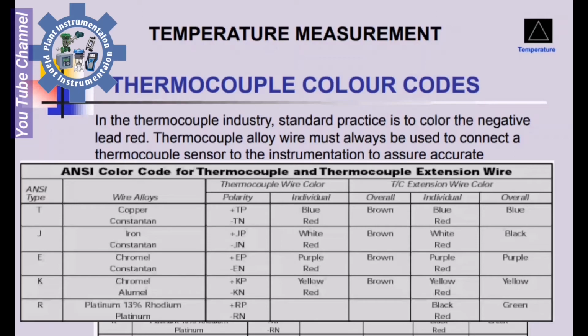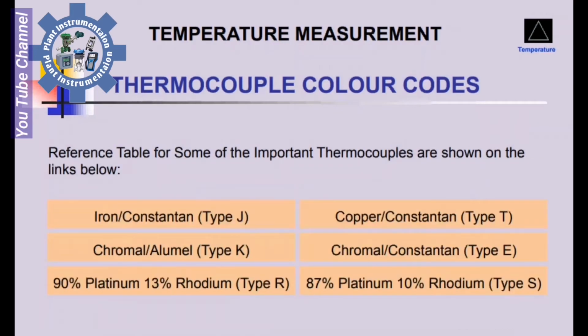K type: chromel-alumel. Polarity: positive KP, negative KN. Individual: yellow, red. Thermocouple wire overall: brown. Extension wire individual: yellow, red. Overall: yellow. Type R: platinum 13% rhodium-platinum. RP positive, RN negative. Individual: black, red. Extension wire overall: green.